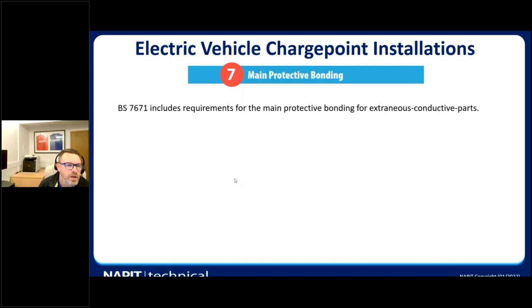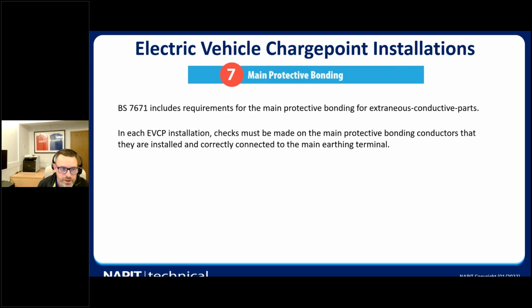Number 7 is main protective bonding, and 7671 includes all the requirements for protective bonding for extraneous-conductive-parts. Each EV charge point installation must be checked to make sure the protective bonding conductors are in place, installed and correctly connected to the main earthing terminal.